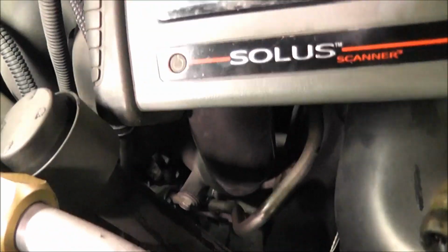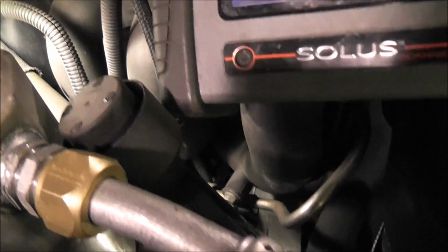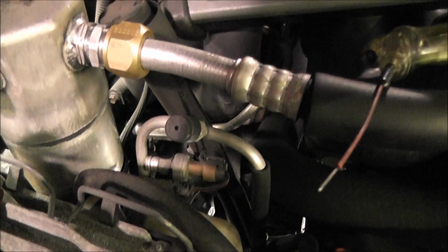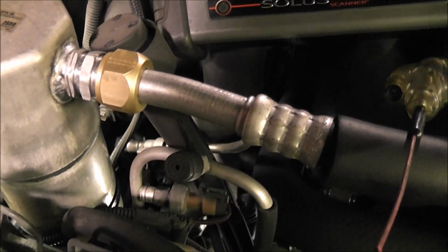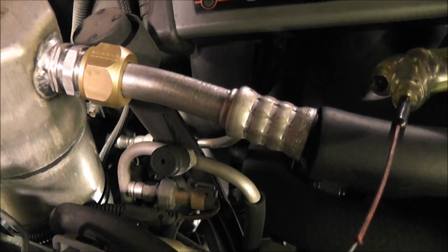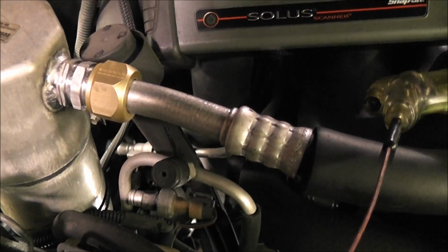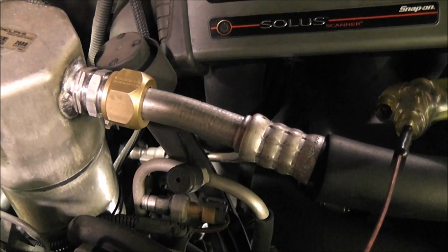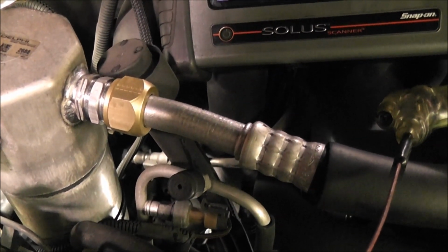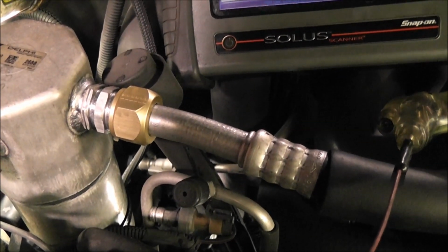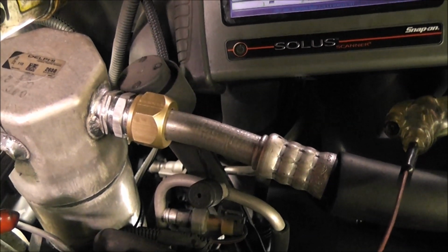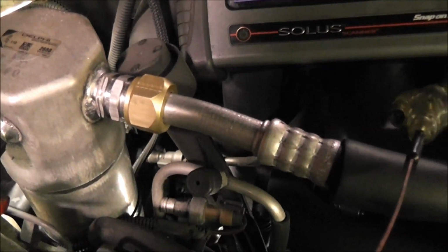This is the air tube. I don't know if you caught that, but when I fired it up, it pushed air or water out of that tube. So chances are it was starting to bind up. It threw too many amps and popped that fuse. I'm going to have to pull that apart and go down underneath and we'll check that.